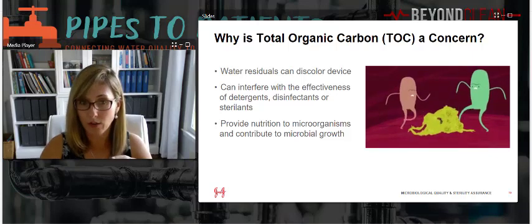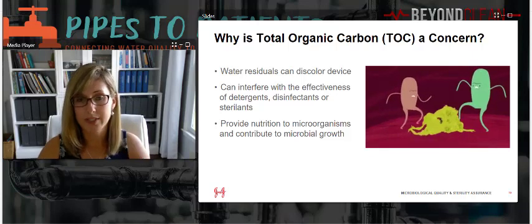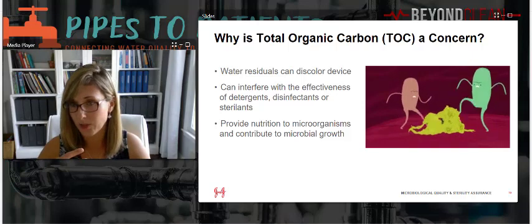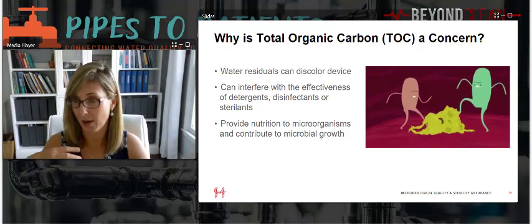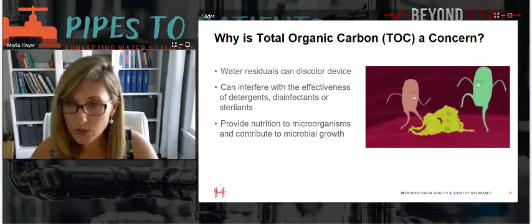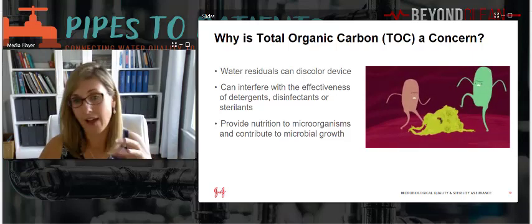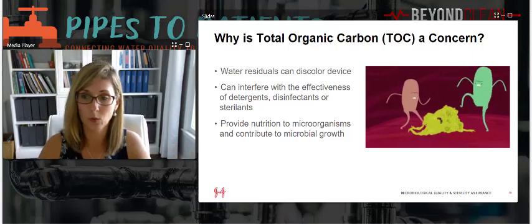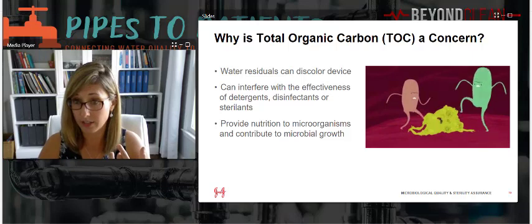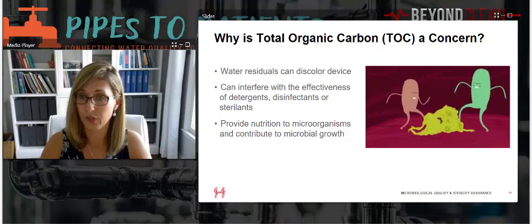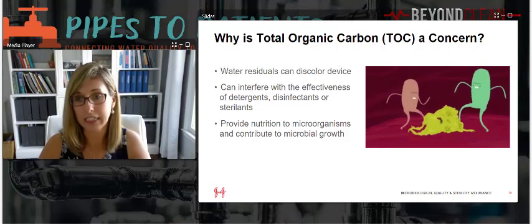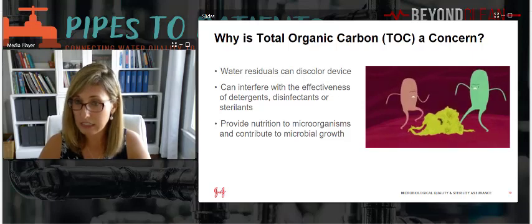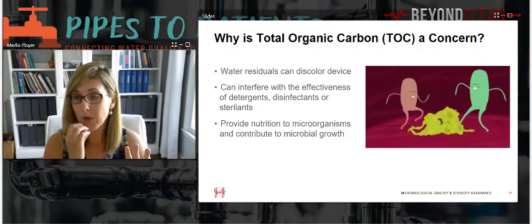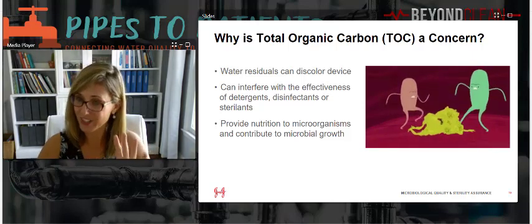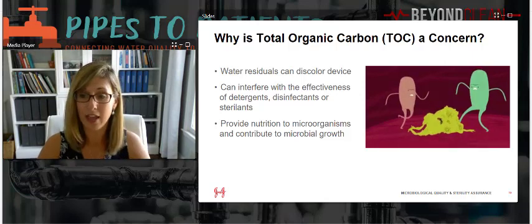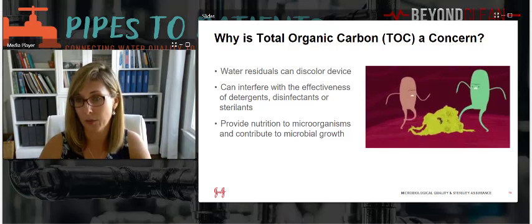When we talk about organic pollutants, we mean total organic carbon, often known as TOC. What happens if we have residual TOC on a device? Well, water residuals can discolor the device. They can interfere with the effectiveness of things like cleaning agents, disinfectants, or sterilants. And more importantly, they actually provide nutrition to microorganisms and contribute to microbial growth.